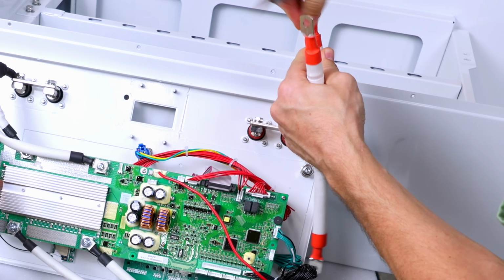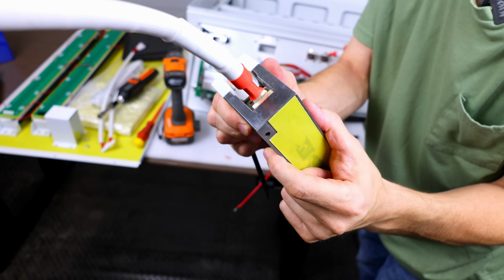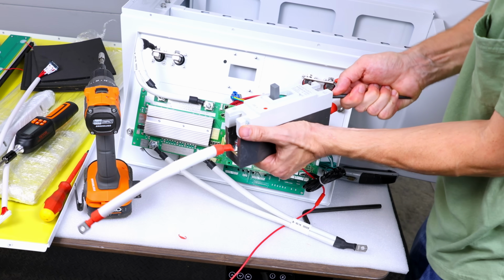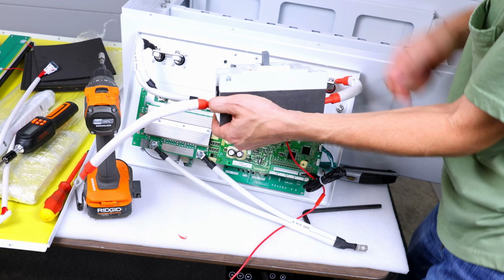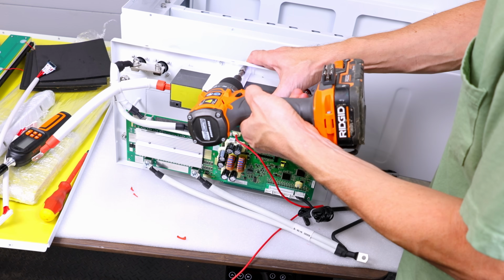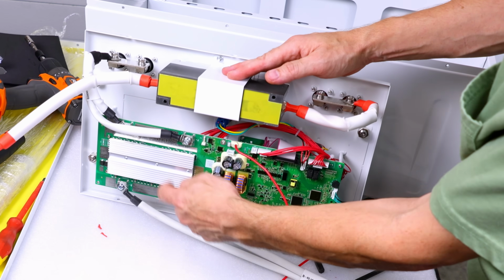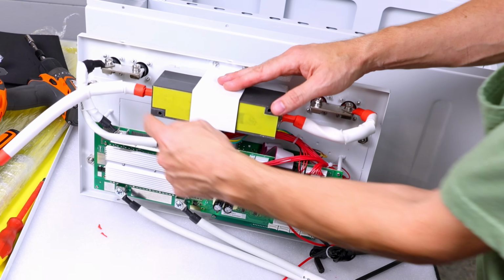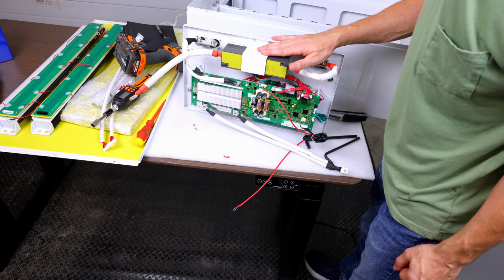Clean this one up too. There we go, we can put this back together. Now we're good and safe. You see a little bit of metal, we'll clear that. I can be confident we're not trapping any insulation under the contact. There we go, I checked these, they're good. All the insulation problems are fixed, everything's torqued down, so we can set this aside and put the rest of the battery together.